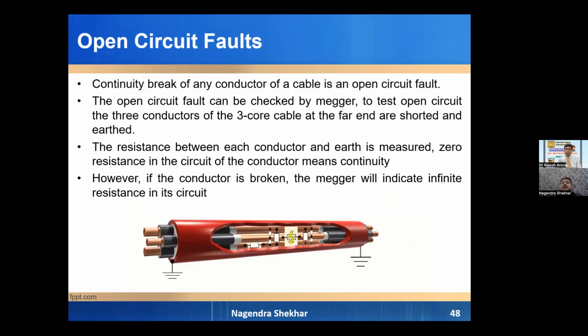Continuity break or open circuit is when the conductor is broken in a cable and continuity is not there. Usually these are very rare faults, but they do occur. I remember one case when a cable was damaged by a JCB while digging. The faulty portion was repaired and the cable was energized, but supply did not reach because the cable was not tested for open circuit fault.